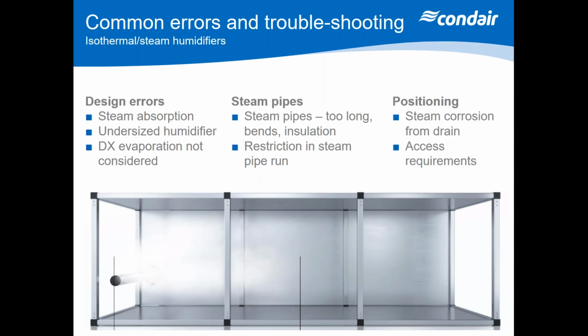Another thing to also consider is the positioning of the unit in terms of its drain. So if you're positioning the unit above a drain, you are going to get corrosion because you're going to get flashing steam off the drain. Also, it's very important to understand where you're putting these units outside to make sure you have the correct type of enclosure and also the correct heating, ventilation and thermostats to control the level of the temperature within the enclosure above 5 degrees. If it goes below 5 degrees, then you're going to see sweating on the boards, which can damage the boards.